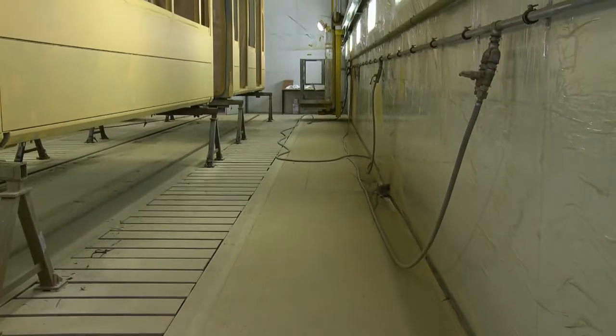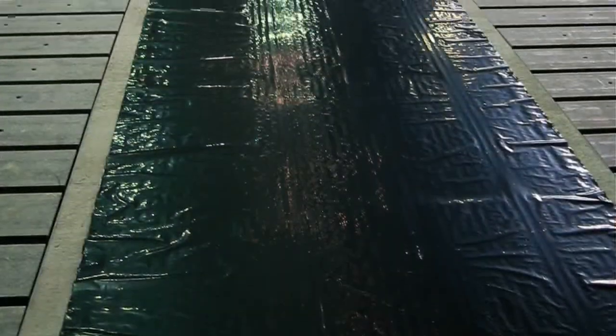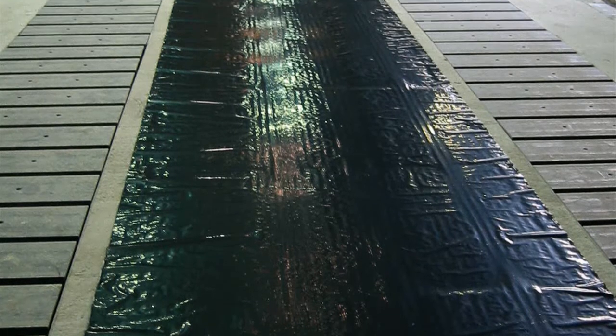Coating technicians with paint on their shoes also soil the walkway, the maintenance of which was made much easier in this cabin. The so-called quick-clean foil is held down on the floor through under-pressure, created by an in-floor duct connected to the suction side of the exhaust air system. Once soiled, the foil can be removed and replaced. This solution eliminates encrusted flooring.